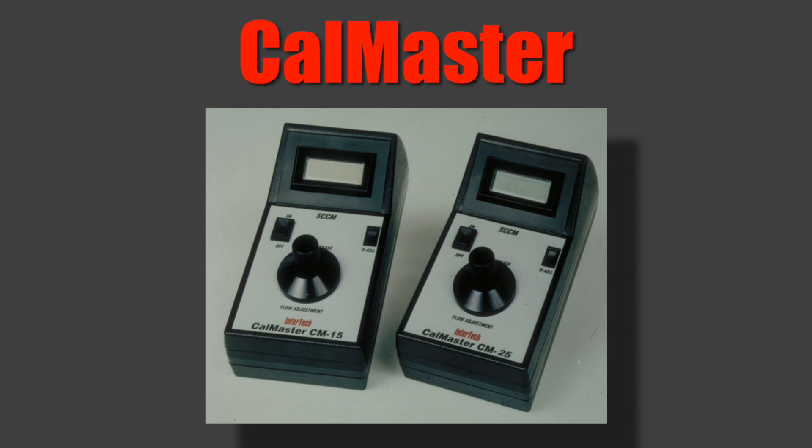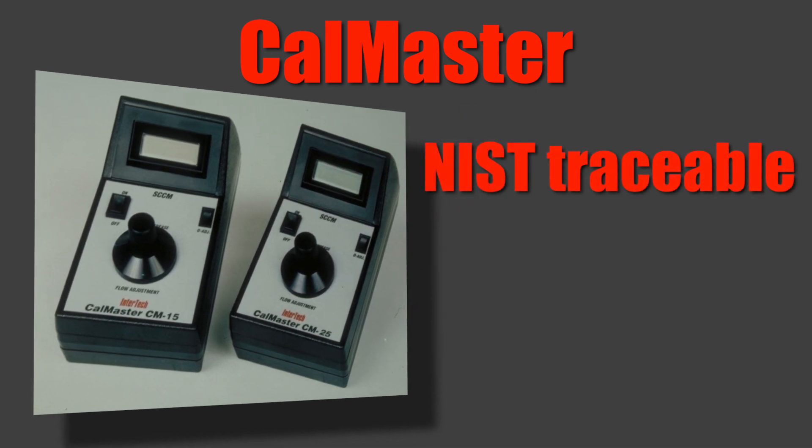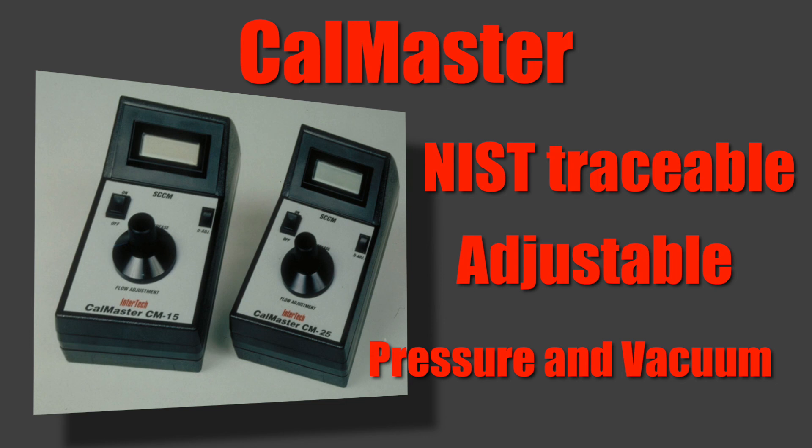In addition to the M1075 and instead of purchasing a single calibrated orifice for calibration that's set at one test pressure and flow rate, Intertech offers the CalMaster. The CalMaster is a NIST traceable adjustable calibration standard that offers a wide range of calibratable flows and test pressures, including vacuum. The CalMaster eliminates the need for ISO tracking of numerous orifices and offers the user a single certified source for all your leak testing application calibrations.